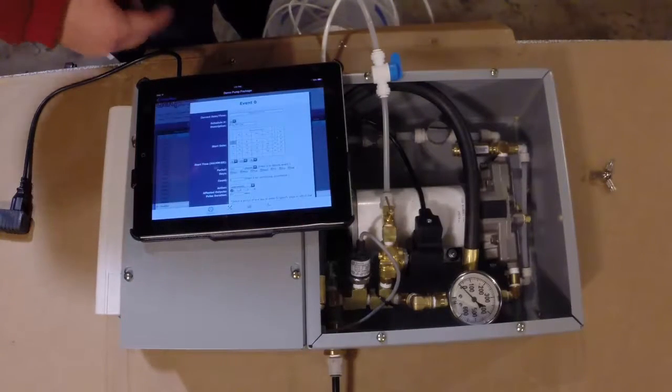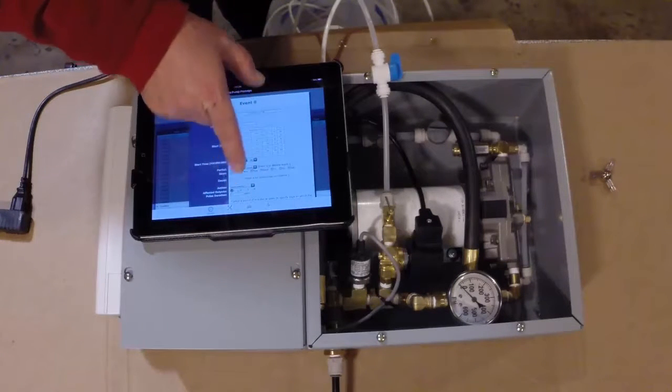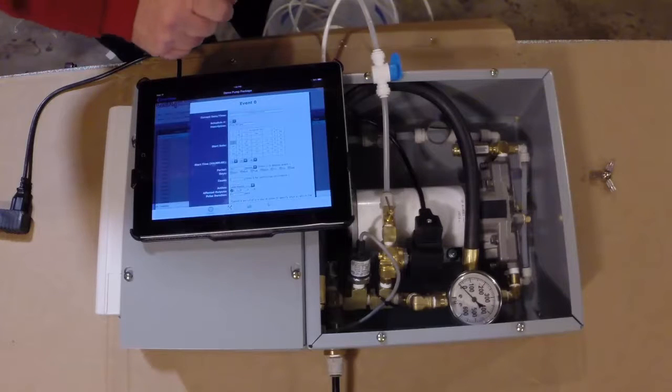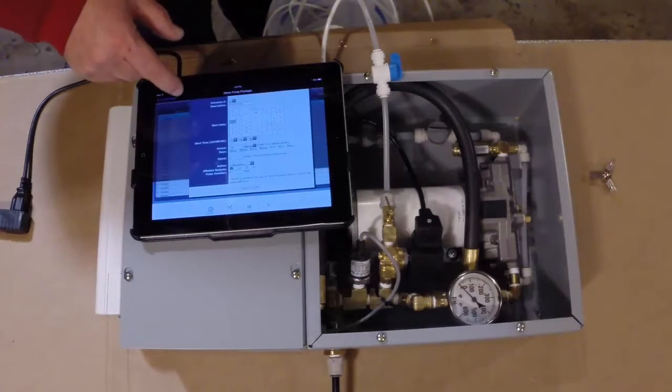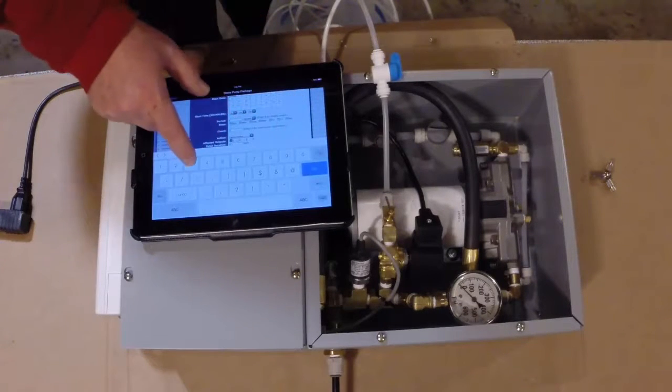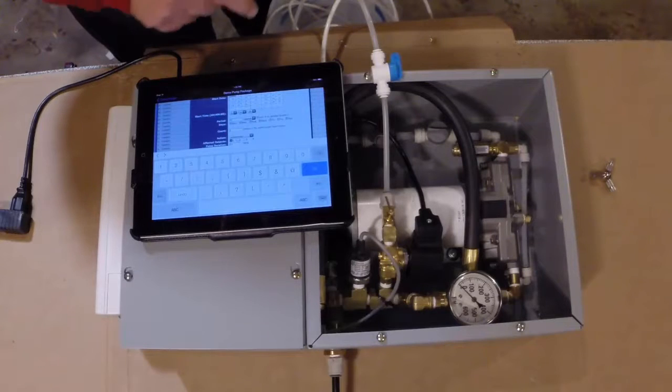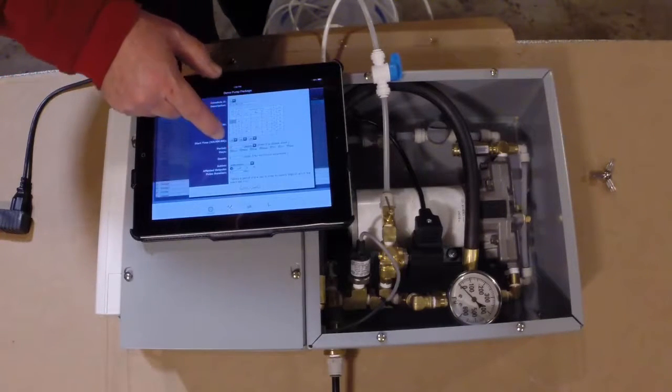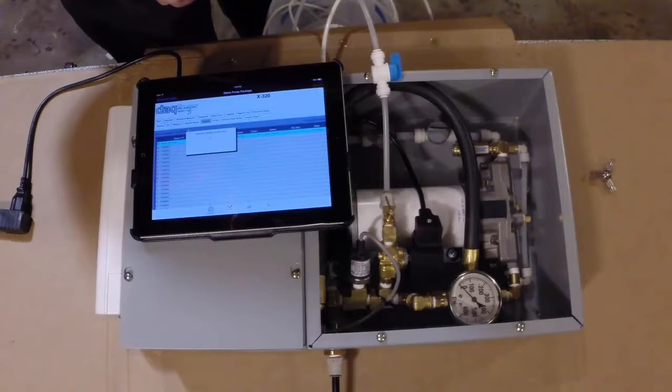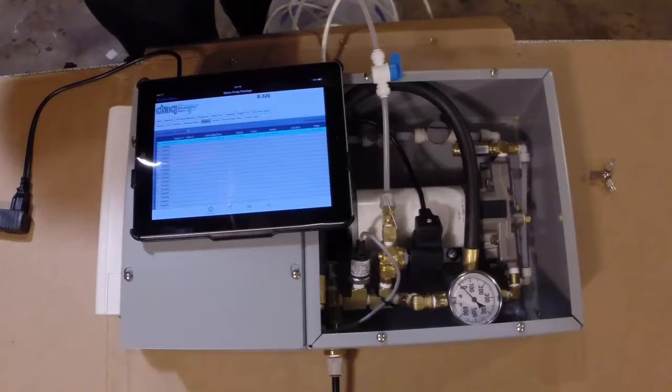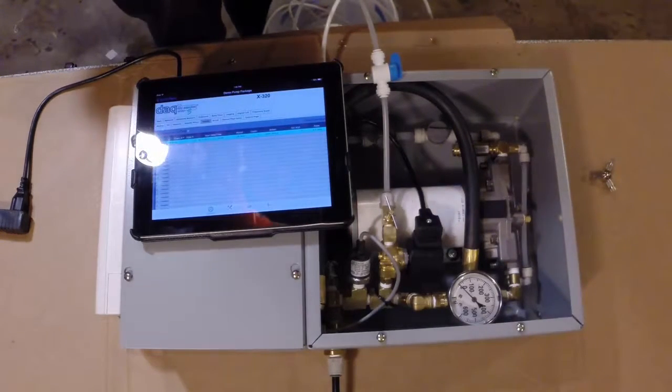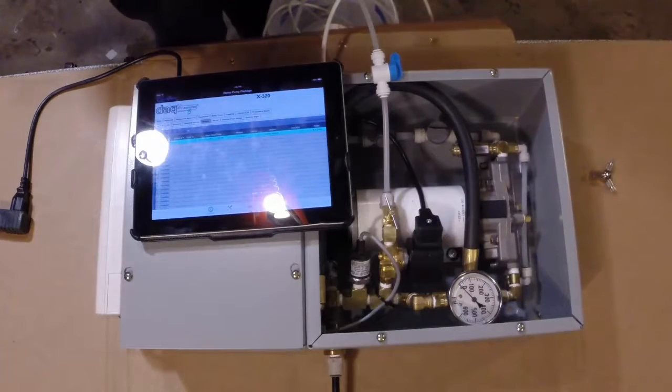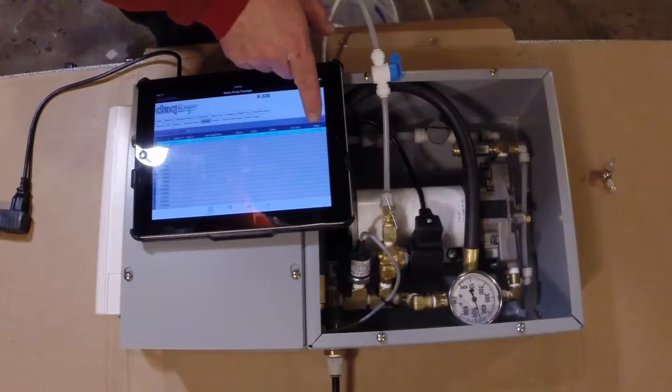If I take a look at that event, right now we're set to run the pump for 6.5 seconds on a pulse every 1800 seconds. Well, let's change this down to 30 seconds. I'm looking at this upside down. And we'll update that. Done. Now, if everything's set up right, this unit should run every 30 seconds.